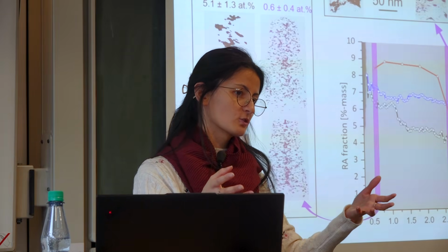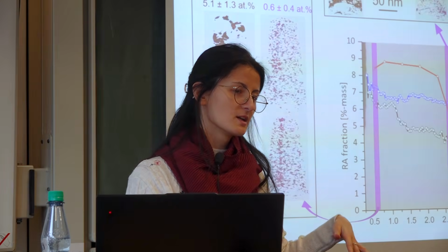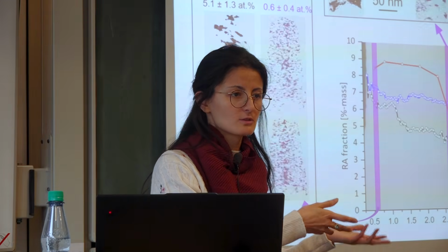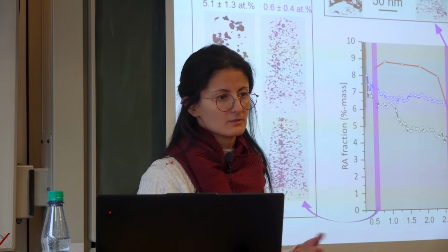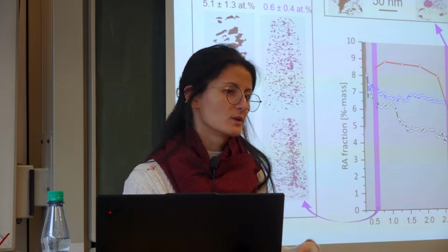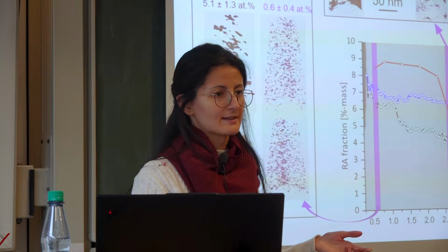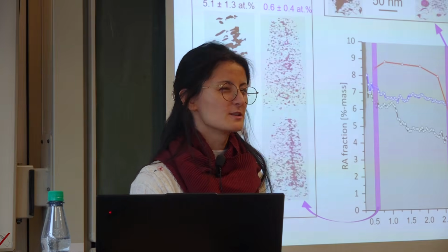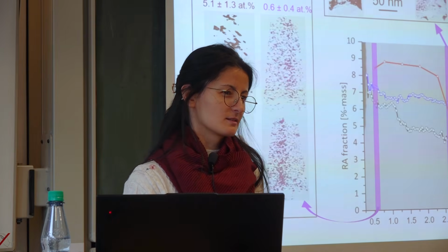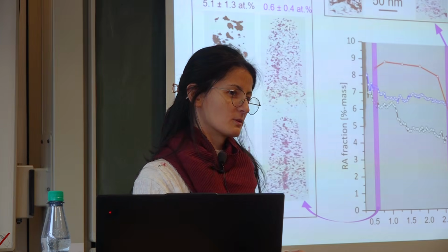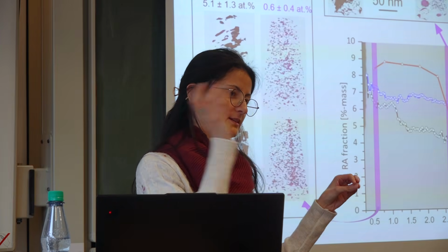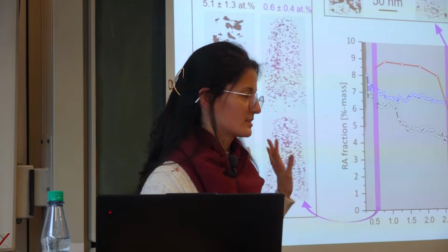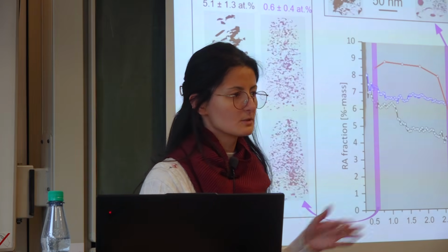So this detector is covered homogeneously, so it doesn't have any impact on, for example, the light materials being less detected. The concentration we have is still correct because every element is impacted the same way. Yeah, it's not like EDS, where we do not have the same excitation of light atoms and then we don't detect them well or with a bad accuracy, for example. This doesn't happen. Here we detect all the elements with the same accuracy.